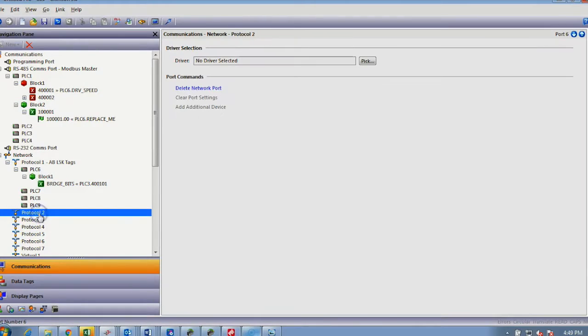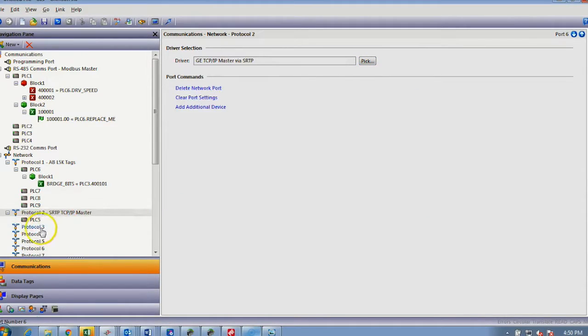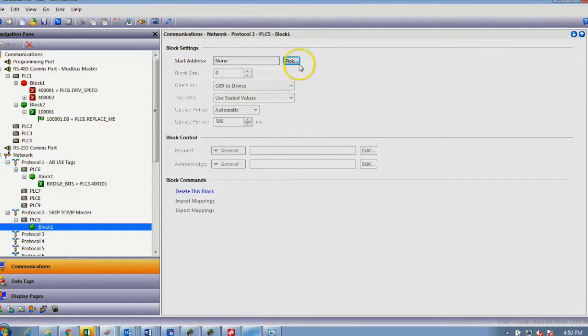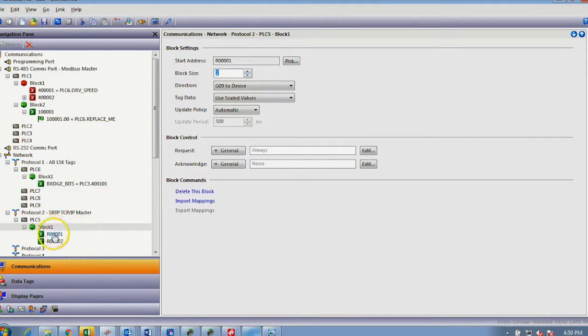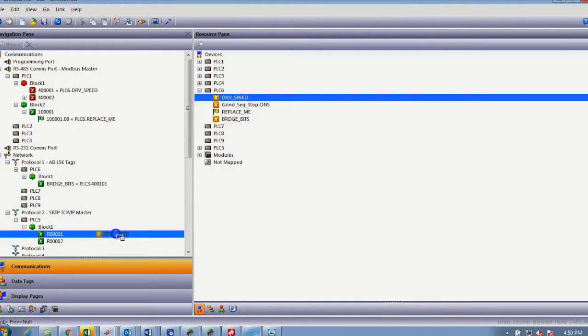Another obvious application that is done quite extensively is not necessarily from, say, a field orientated bus, but from two prominent PLCs. We have our Allen Bradley, but another very large installed PLC would be the GE, using the SRTP driver. Quite simply, very, very simple format. In this particular instance here, we're using the SRTP TCP/IP driver, which of course uses the memory-based addressing format. So we'll use the percent %Rs, and as you can see, the entire memory format will be sitting here.